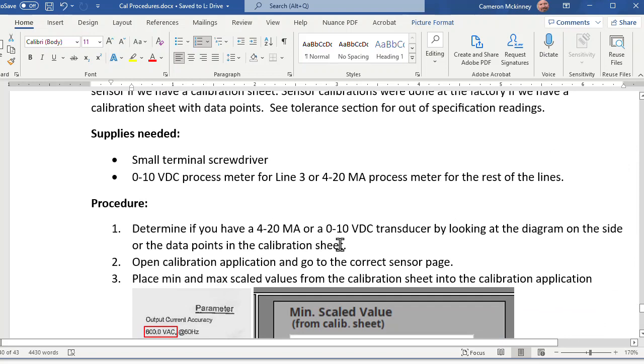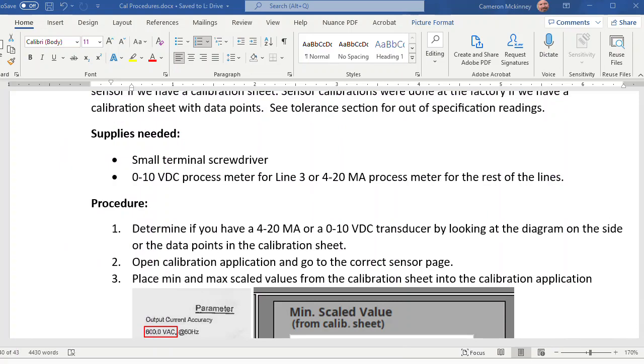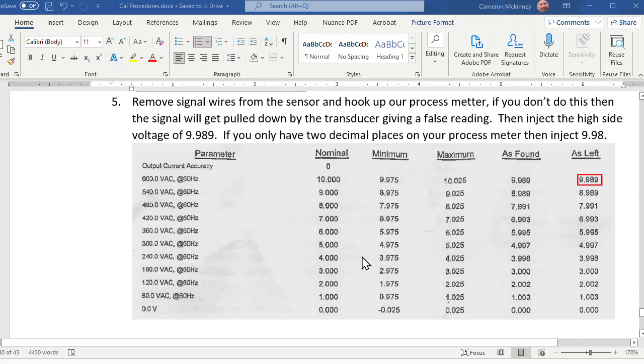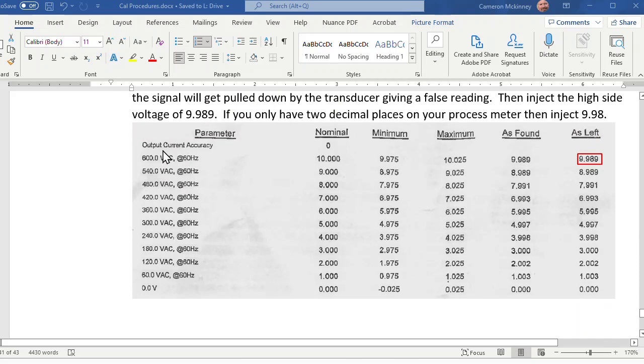We've determined what it is. We're going to look at our calibration sheet, which I believe is right here, a screenshot of that. So at 600 VAC, they ran through the calibration and they had a min and max, as found and as left. That's where they left it. So 9.989 volts should equal 600 VAC in our scaling. And then, of course, 0 equals 0 volts.